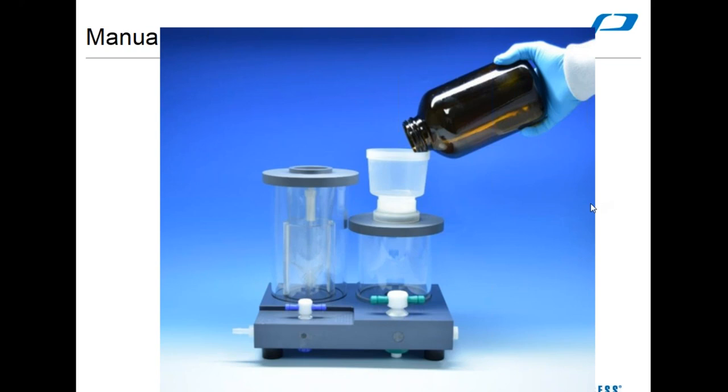Can multiple units be combined together to handle larger sample load? Yes. If you look at that picture, you'll see this plug here. That can be removed and just put another barb in place. You can chain multiple units together. Someone's asking about stearic acid adhering to plastic surfaces. Yes, it does. Almost all oil and grease will adhere to plastic surface in some manner. That's why it's very important that you follow the rinsing procedures as they're outlined in the method.